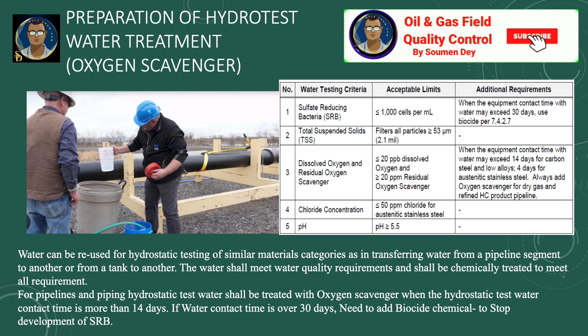Chloride concentration should be less than 50 ppm for austenitic stainless steel, and pH value should be greater than 5.5. Water can be reused for hydrostatic testing of similar material categories — such as transferring water from one pipeline segment to another or from one tank to another — provided it meets water quality requirements and is chemically treated. For pipelines and piping, hydrotest water shall be treated with oxygen scavenger when contact time is more than 14 days. If water contact time is over 30 days, biocide chemical must be added to stop the development of SRB.